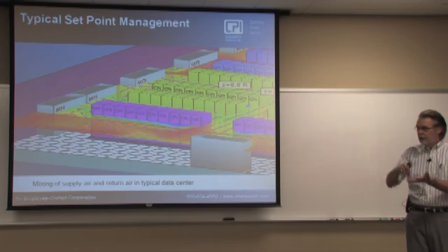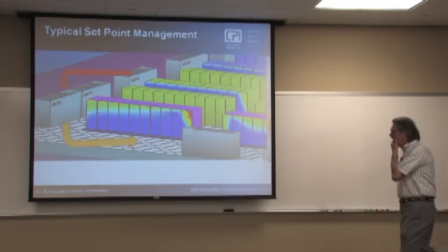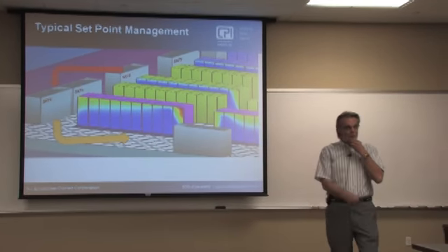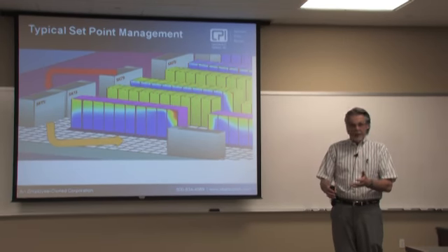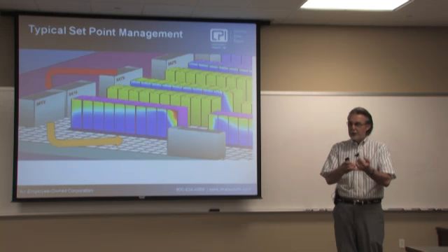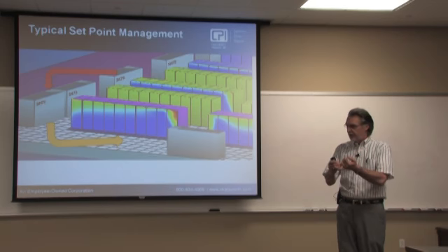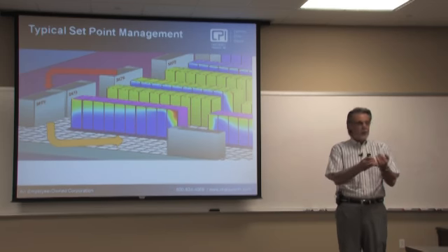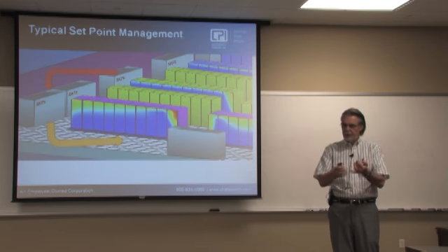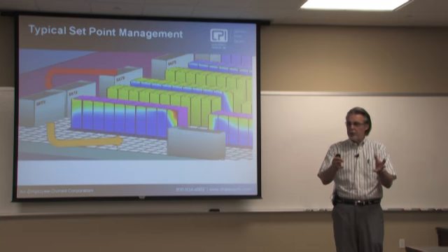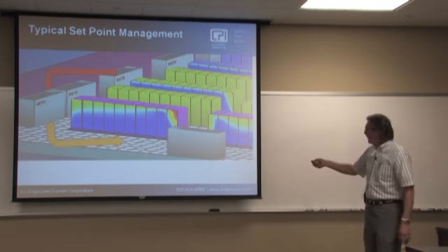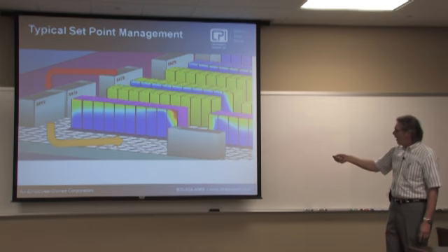Kind of, sort of. And the fact of the matter is, they're usually wrong, because some of the servers will get air that's too cold, and that's going to give them condensation problems. They'll be below dew point and actually make water inside those servers, and they'll get hot spots as well.